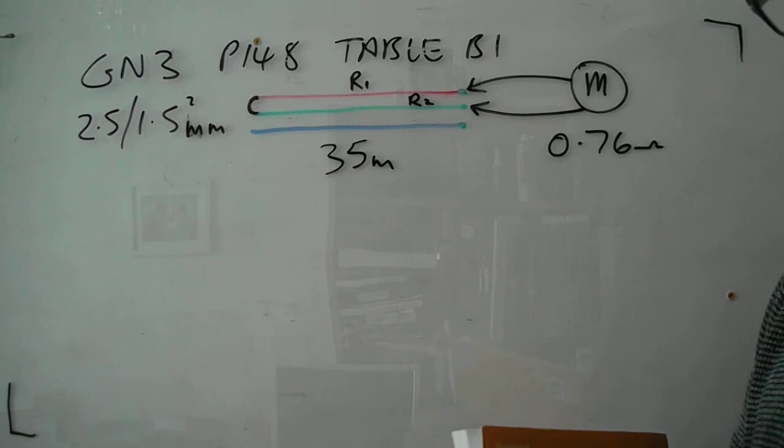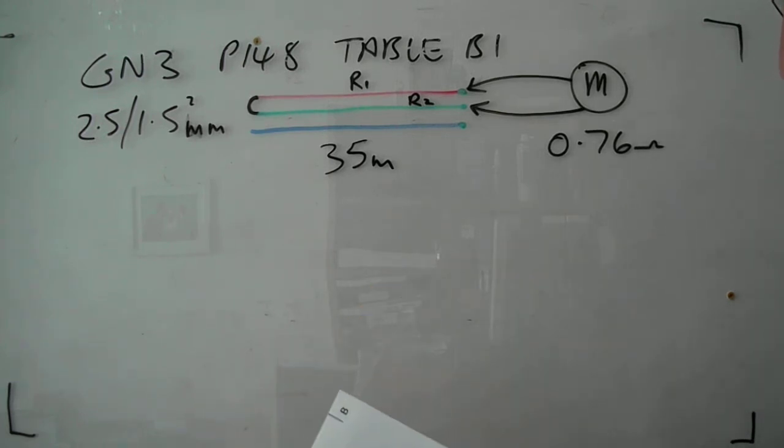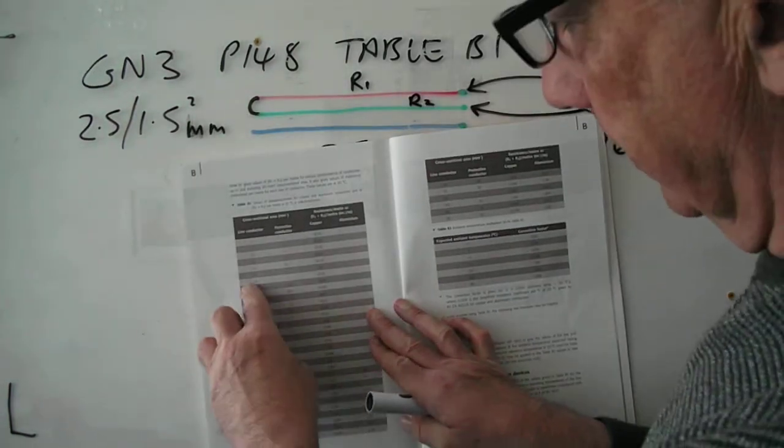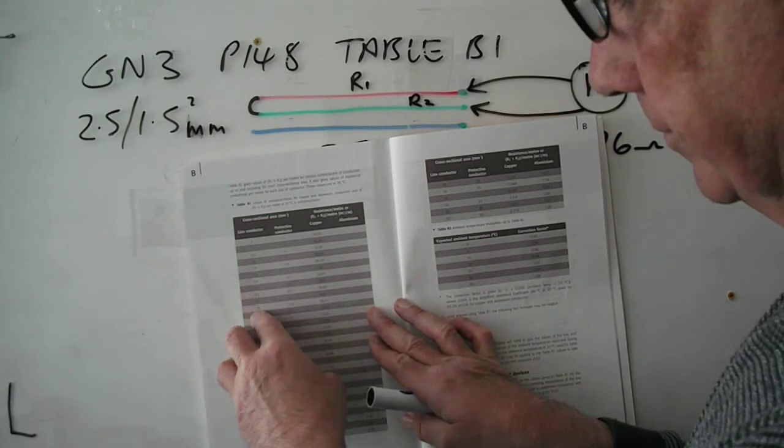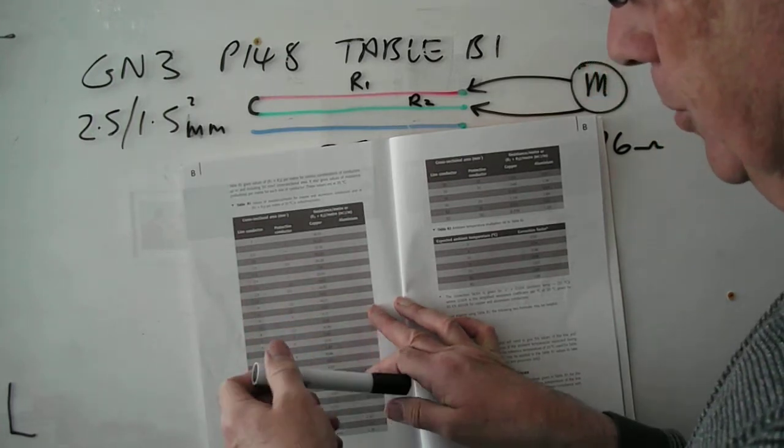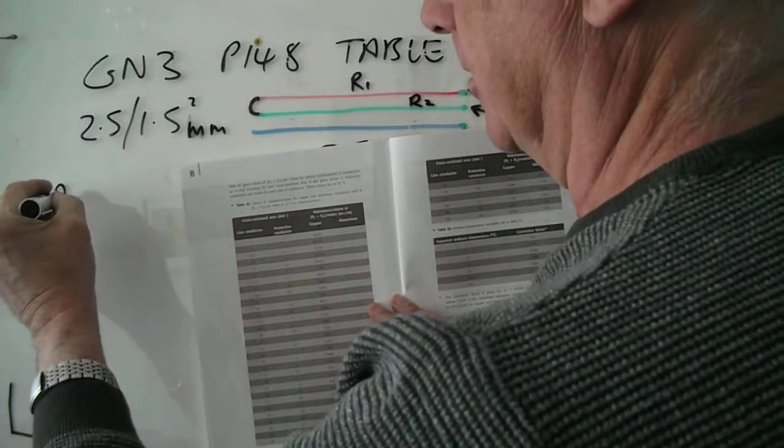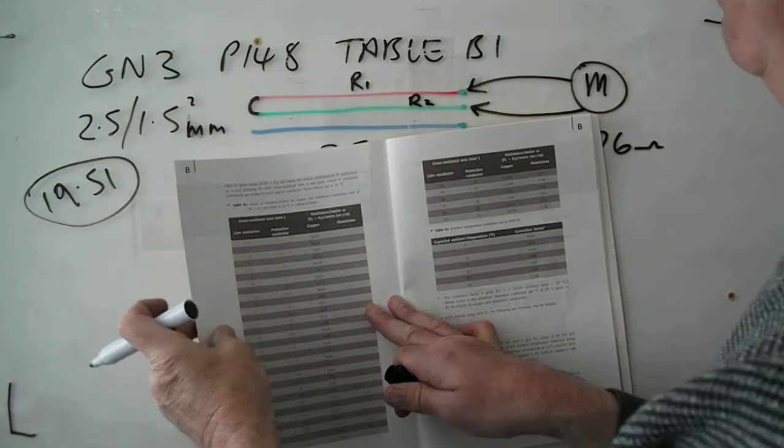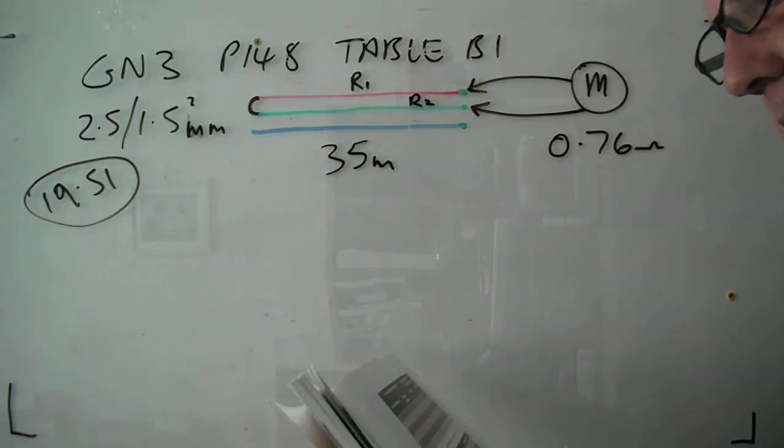OK, so the way we can find that out is to look in table B1 again and look down for 2.5 and 1.5 cable which is here. And the figure in the book is 19.51 milliohms per metre.